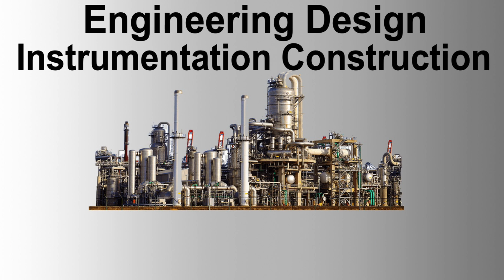Testing and verification. After termination, each connection shall be tested for continuity and insulation resistance to ensure integrity and proper installation. Any connection found to be defective or not meeting the specified standards shall be re-terminated and retested. Test results shall be documented and submitted for approval.